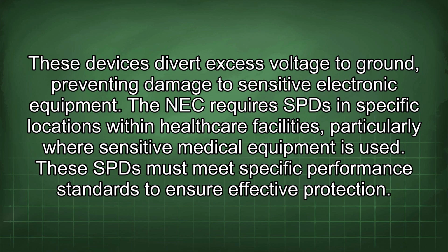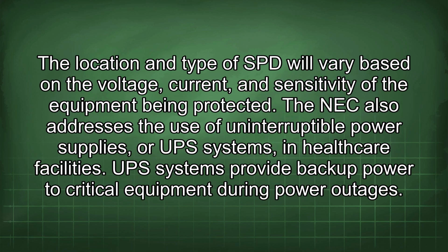The NEC requires SPD in specific locations within healthcare facilities, particularly where sensitive medical equipment is used. These SPD must meet specific performance standards to ensure effective protection. The location and type of SPD will vary based on the voltage, current, and sensitivity of the equipment being protected.